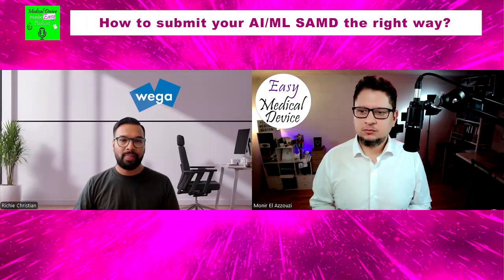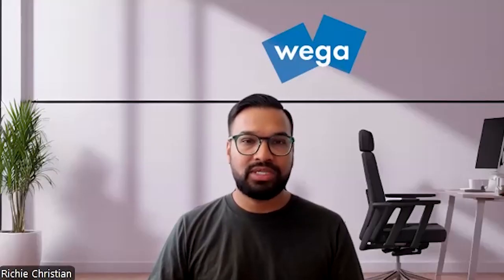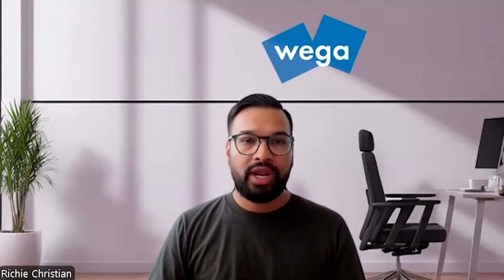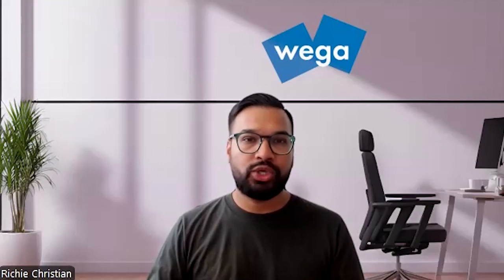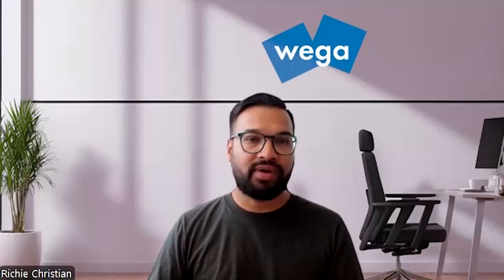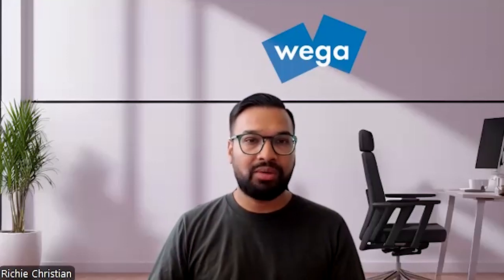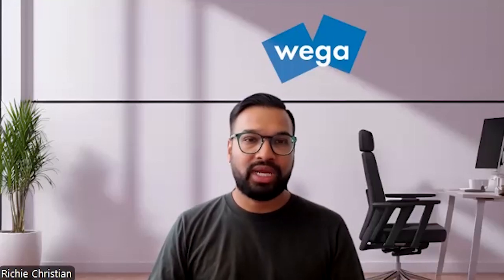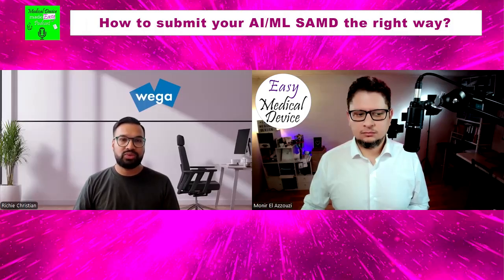Yeah, absolutely. I think this goes back to that human-AI team that is constantly working together. There are things that the AI/ML system is really good at doing, and then there are things that the clinician is really good at doing. So where do you have these handshakes, and where do you involve this human in the loop to make and approve any decisions that your AI/ML system is making? So that interaction, and where that final decision making lies, is really important from a regulatory point of view, because if you have a fully autonomous system, then the regulators are going to expect a lot more rigorous verification and validation to prove that everything is working as it should.